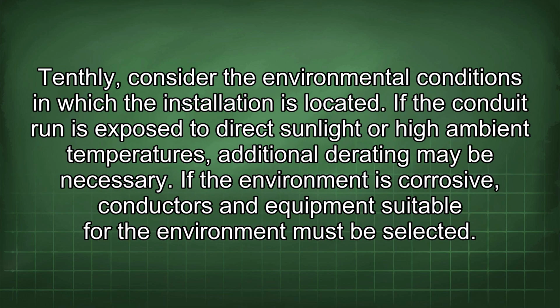Tenthly, consider the environmental conditions in which the installation is located. If the conduit run is exposed to direct sunlight or high ambient temperatures, additional derating may be necessary. If the environment is corrosive, conductors and equipment suitable for the environment must be selected.